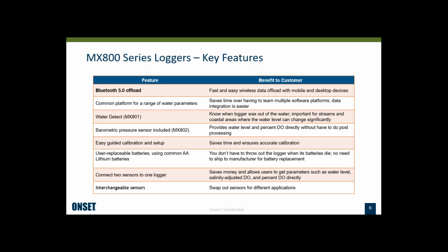The MX801 has the ability to detect whether it's in the water or not. It records that as an event every time it goes into the water, as well as events when it comes out of the water. This is useful for tidal applications or streams where occasionally the water level can go down so low that the logger is no longer in the water, and this is a way for the user to know that. The 802 logger, on the other hand, sits above the surface, so it does not have the water detect feature, but it does have a barometric pressure sensor, which is useful for things like calculating percent dissolved oxygen directly without having to do post-processing. So that saves users that post-processing step.